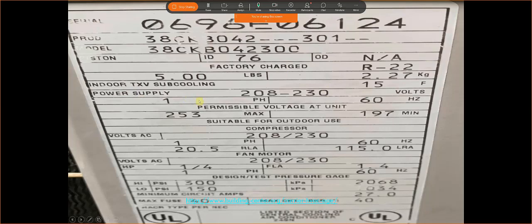My power supply is feeding it 208 to 230, single phase, 60 hertz. This is very common for residential applications. It's always going to be a 220. 220, 230, the words are used interchangeably, but we know that it's going to have two electrical lines coming into the system. The 60 hertz only applies to us here in the United States. If it was European or somewhere else, we would have 50 hertz. We just know that 60 hertz can be used inside the US.